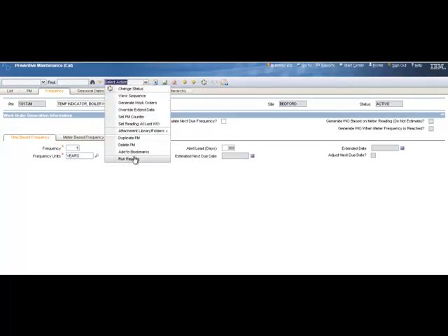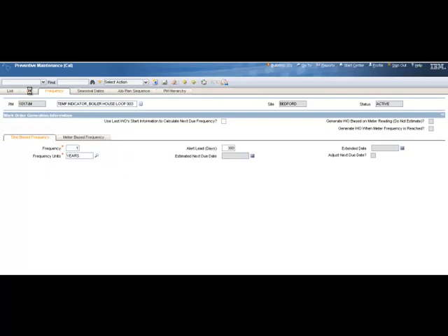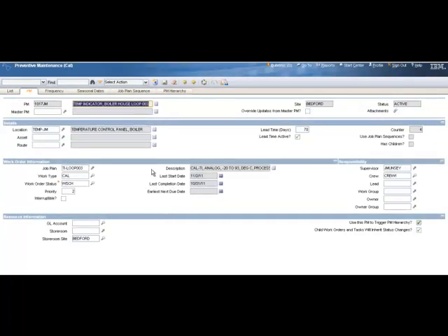In fact, nothing's different. So what the PM cal really does is take your job plan cal, take your data sheet, and when the time is right, it'll create a work order for that specific location or asset on your PM, and give it that calibration job plan and that calibration data sheet, and create the work order for you. And then it tracks how often it's due. So this really is your schedule to get all that stuff done. Click on Go To.